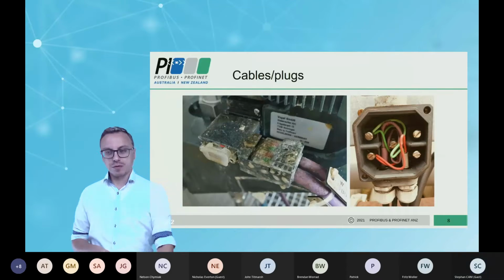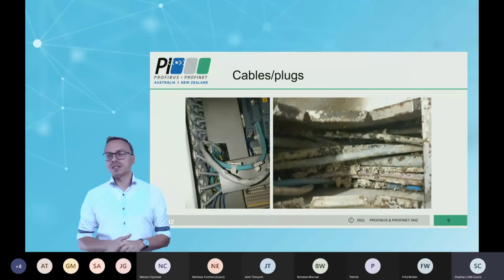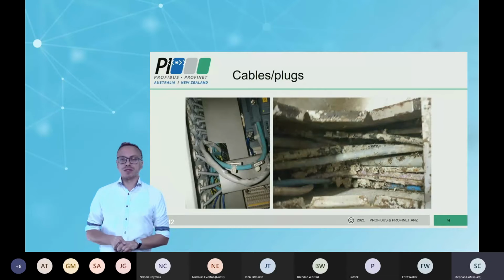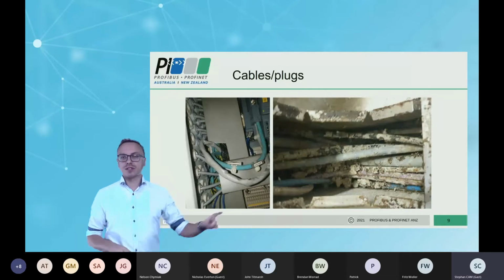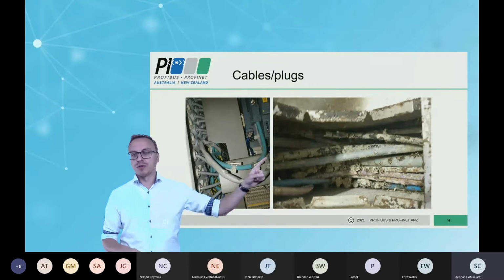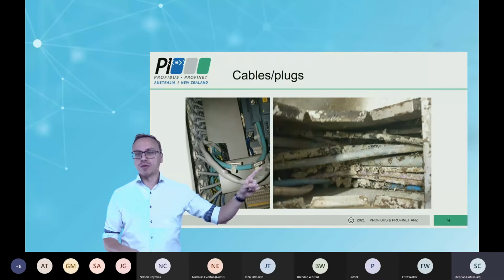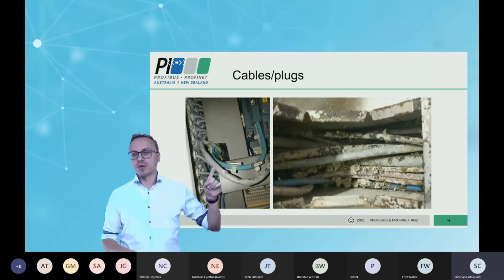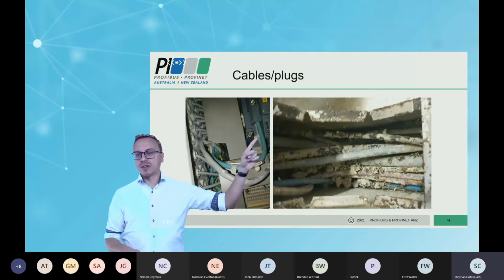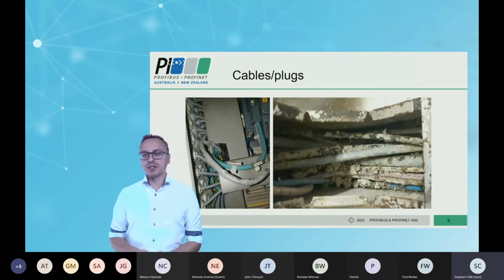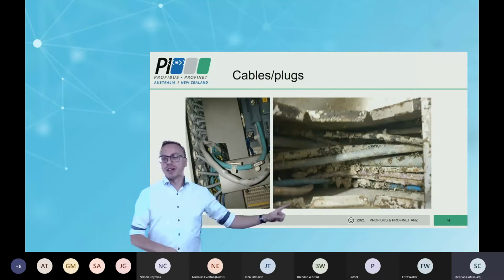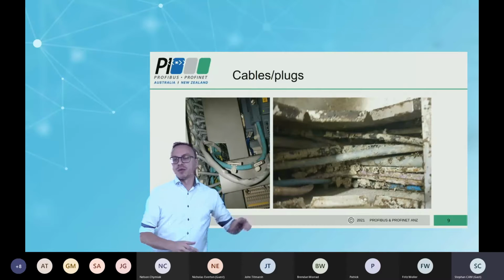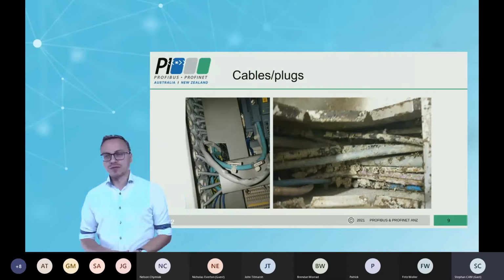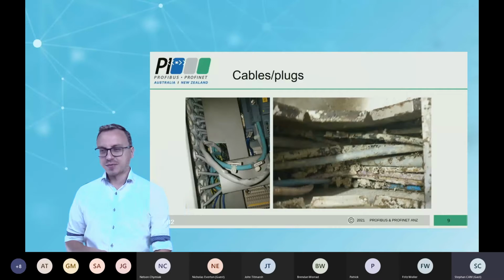So what else? Here are some other examples of a bad installation. You can see in this picture that we don't use the right Profibus cable. This one is a Profibus cable, but the gray one is not a Profibus cable. So this is also a bad thing because of the impedance of the cabling. And here the same: the normal Profibus wire doesn't have enough protection against installations like that.